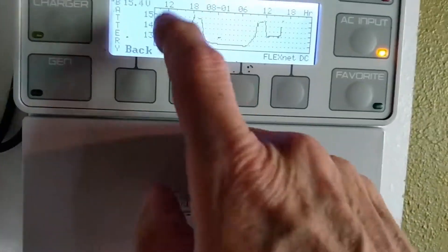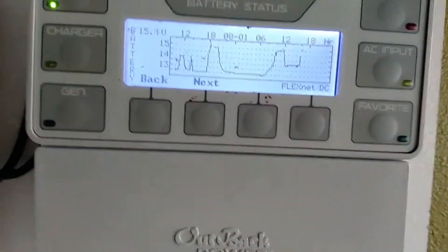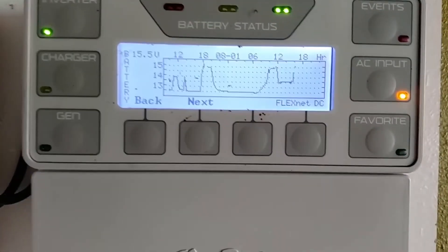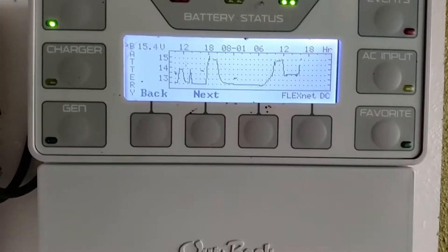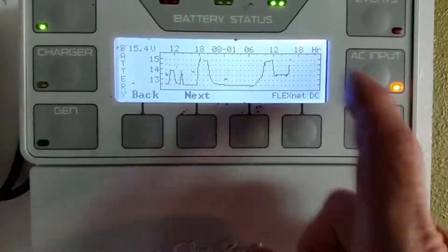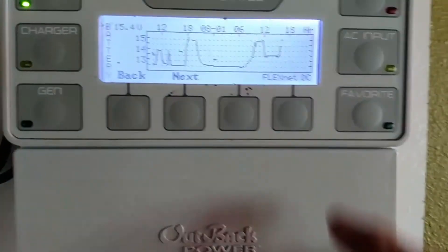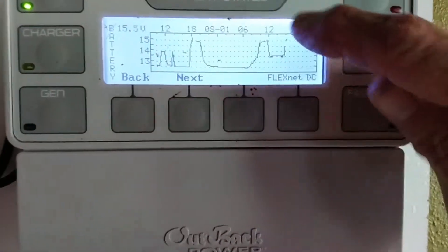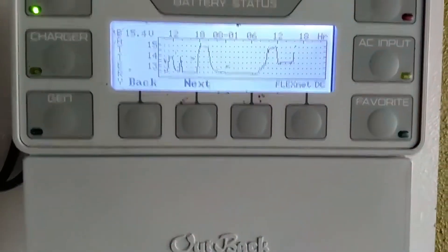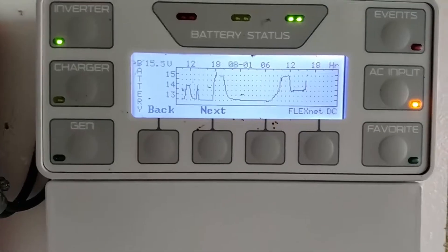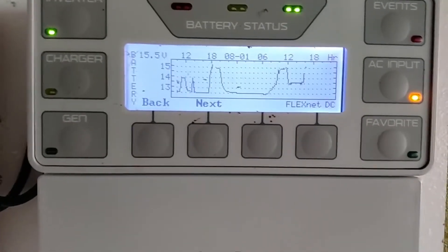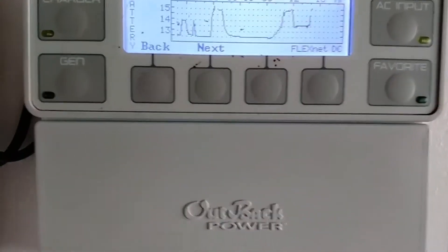It ramped up, took it to the bulk voltage setting, held it there for the absorption period, then dropped it down to float. I then put in an equalizing charge for a little while, and that's where you see that burst on the graph.